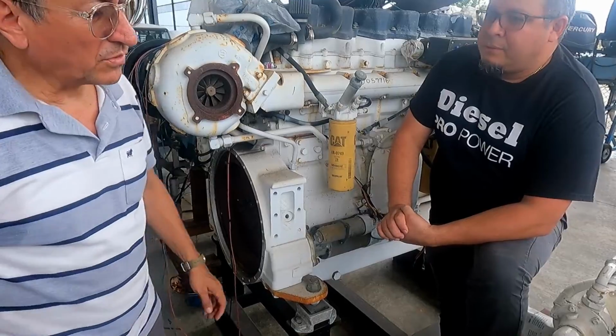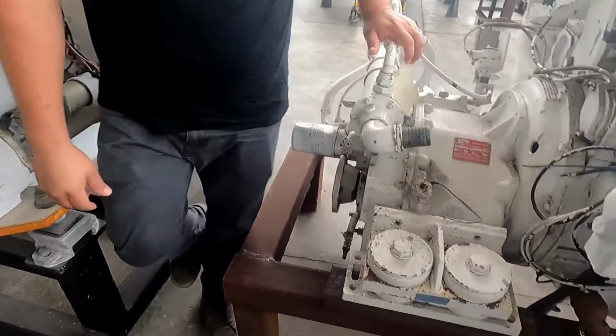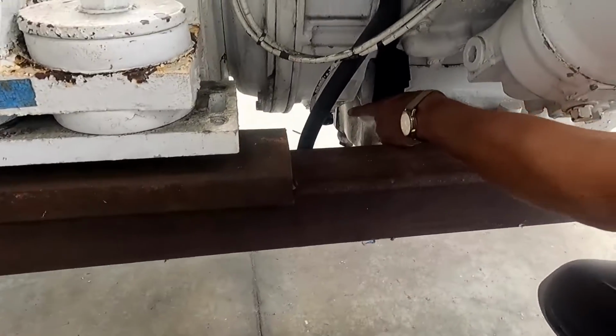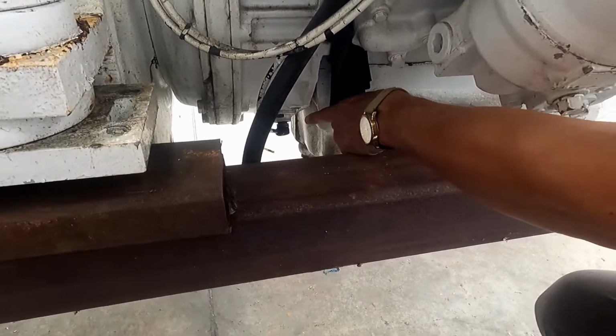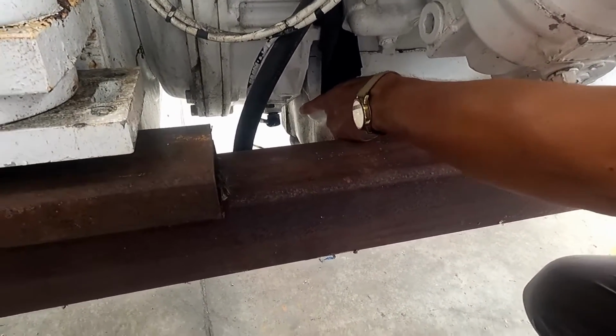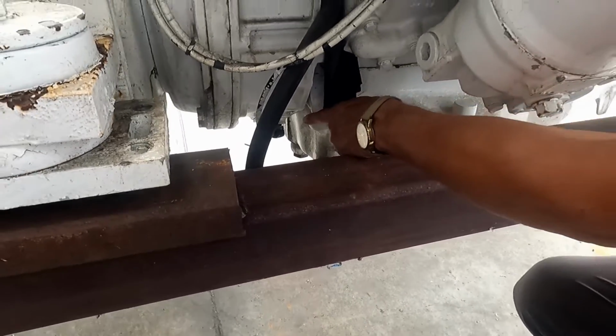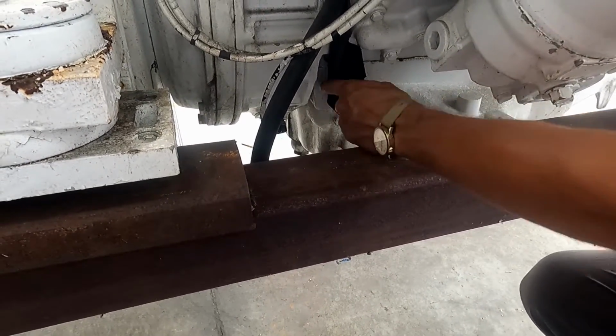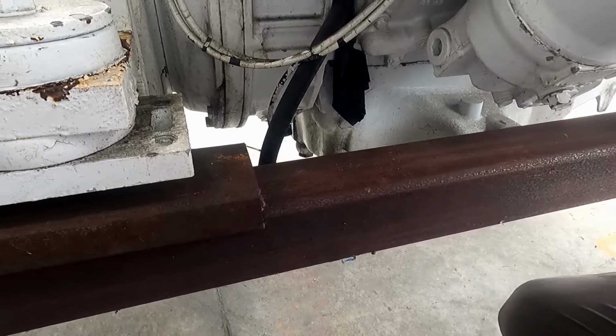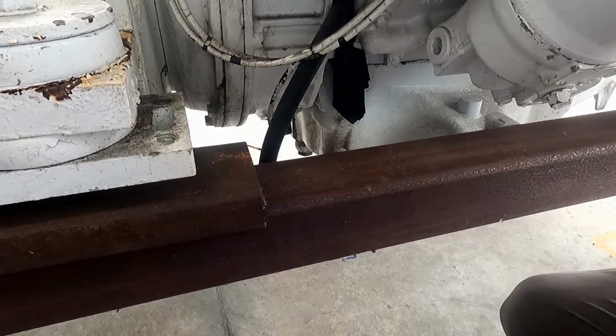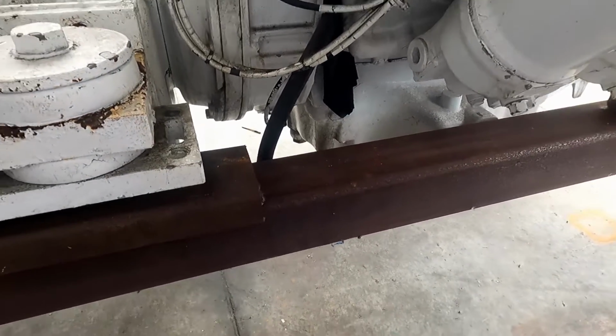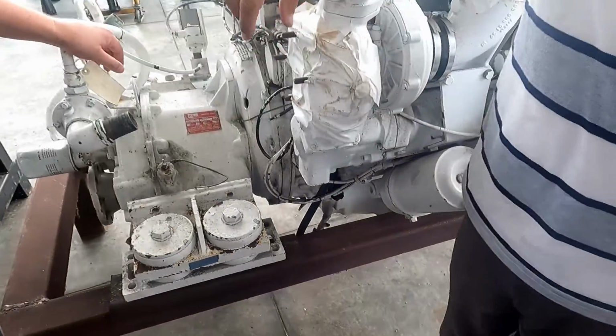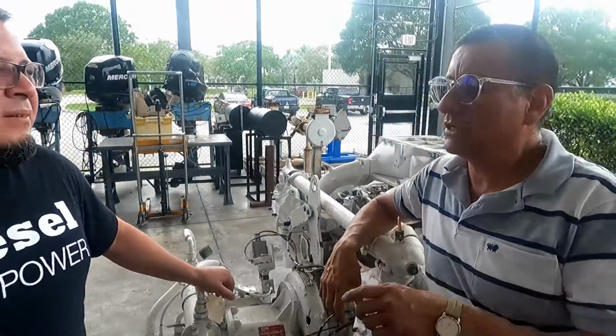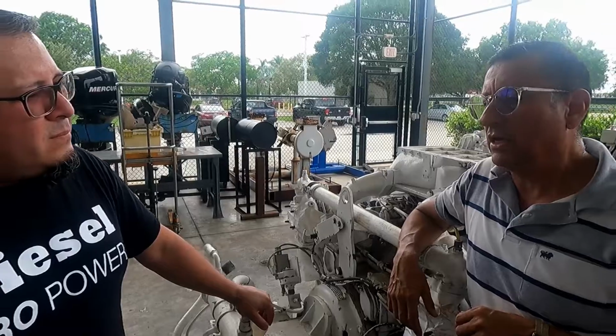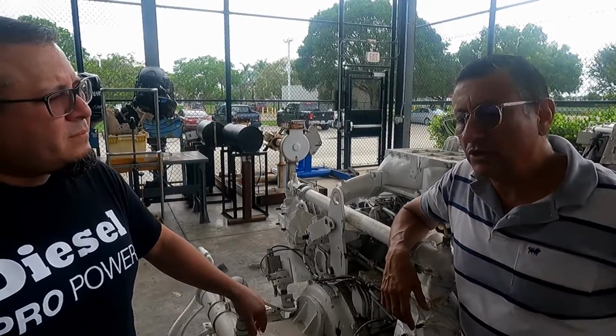The other option, as we mentioned, is when the sensor is on the bottom, like this — that's not good, not recommended, just because of the location. It's too dangerous; sometimes it can break, and you don't want that on an engine. When that sensor is located in the bell housing for a generator, it's used for two purposes: to read RPMs and to read frequency, since it's a generator — 50 hertz or 60 hertz.